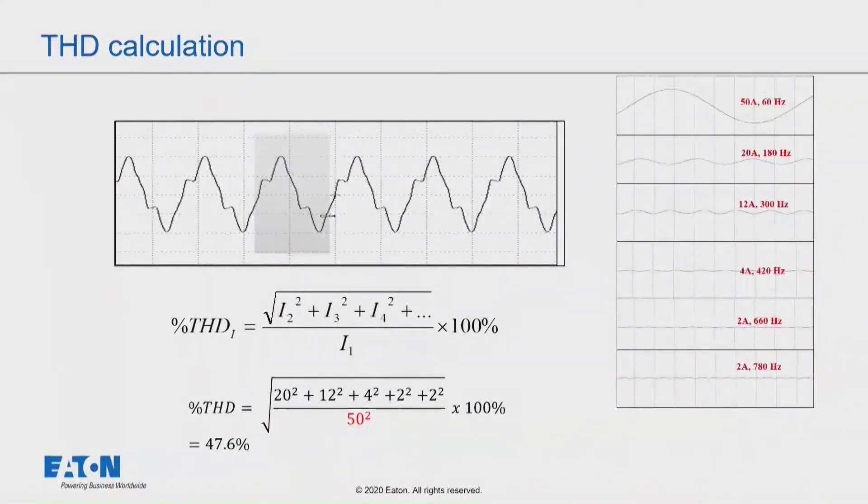But if you think about it, the actual harmonic amps are the same. So don't get caught up in the fact that the harmonic percentages go up. Because at night, a lot of times you'll have a very low 60 hertz part. But the harmonic magnitudes or the actual amps of harmonics could be still the same or maybe about a little bit less.